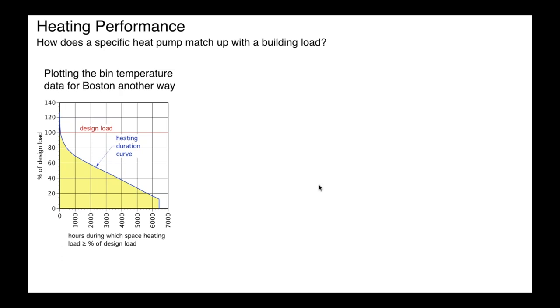On the vertical axis, if we were to put BTUs per hour as opposed to a percent of load, let's say that the 100 here instead of percent represents 100,000 BTUs per hour, okay? Well, the area under that curve, that yellow shaded area, is proportional to the total space heating energy requirement of the building. Now, it doesn't factor in passive solar gains. It doesn't factor in other types of internal gains that could affect it, but simply based on the model that heating load is proportional to the inside-outside temperature difference, that yellow area represents the total space heating energy use over the entire heating season. Okay.